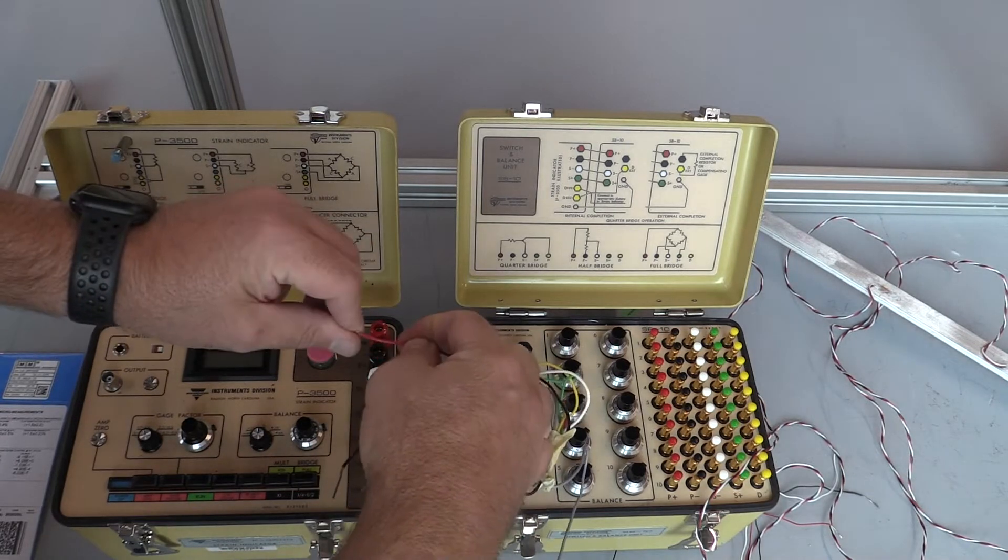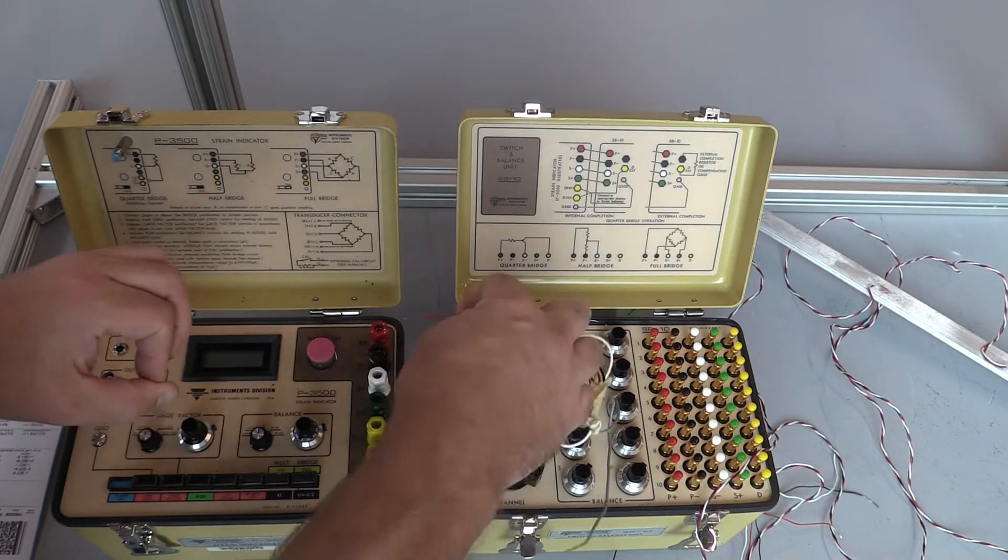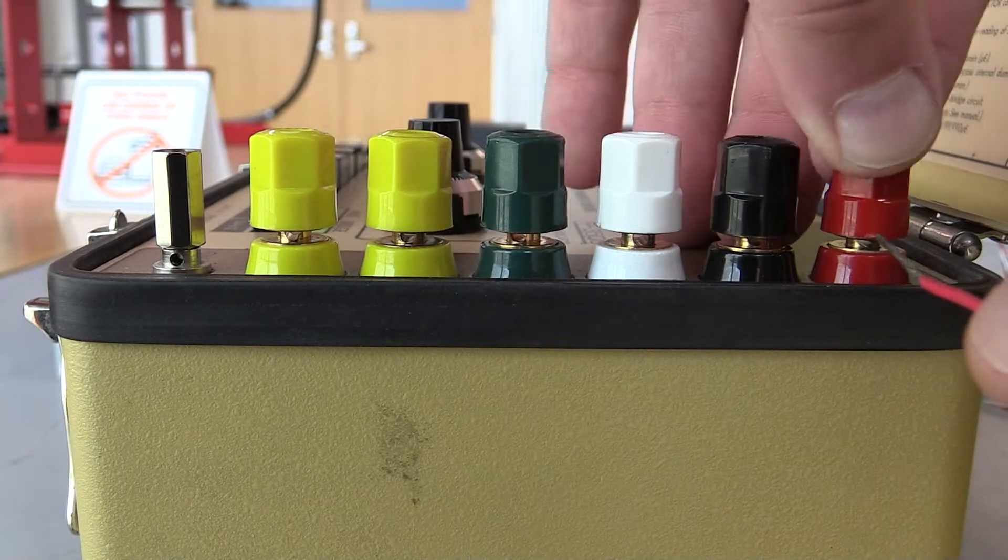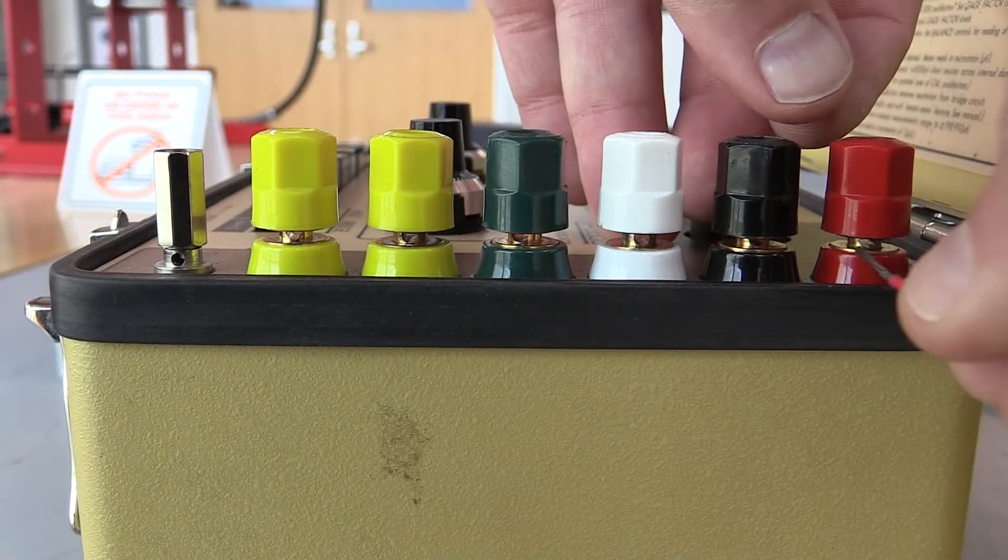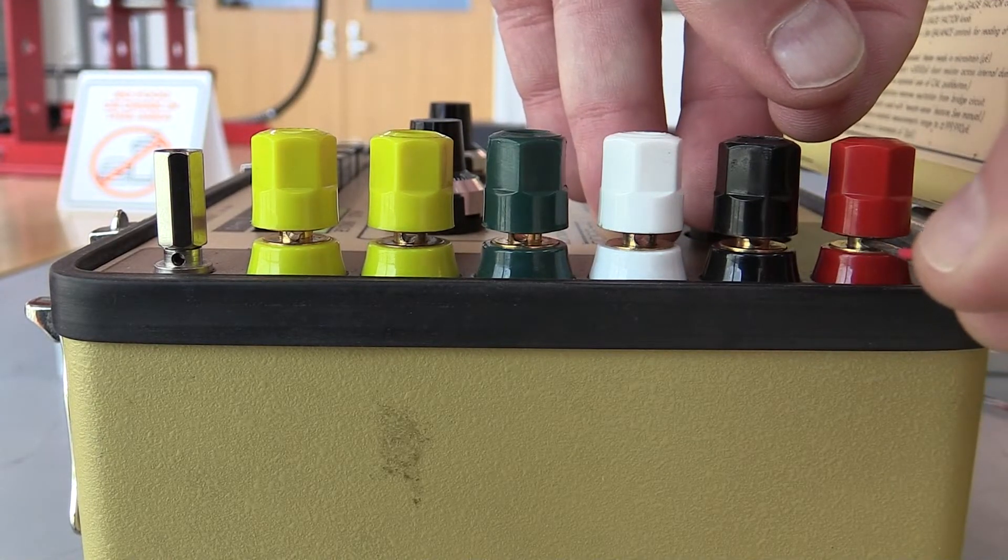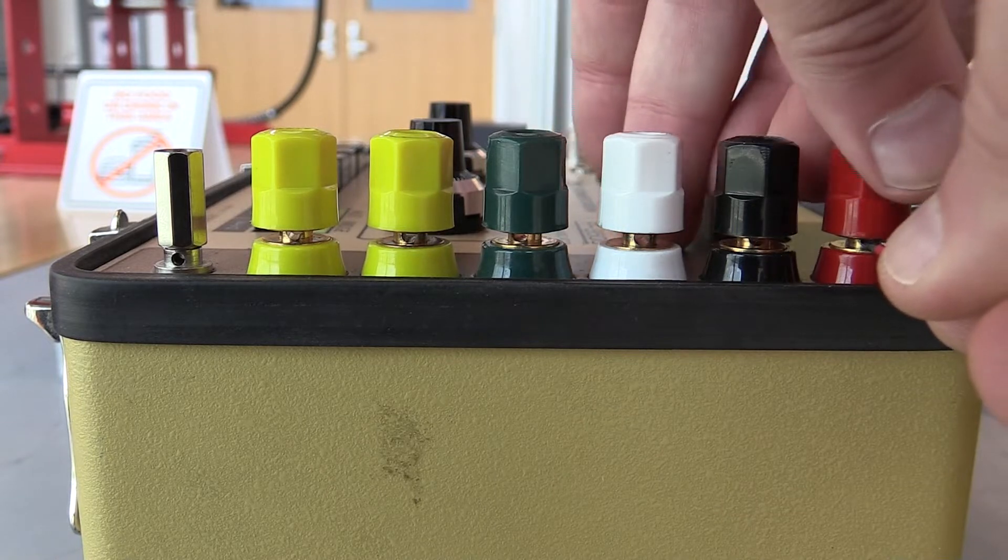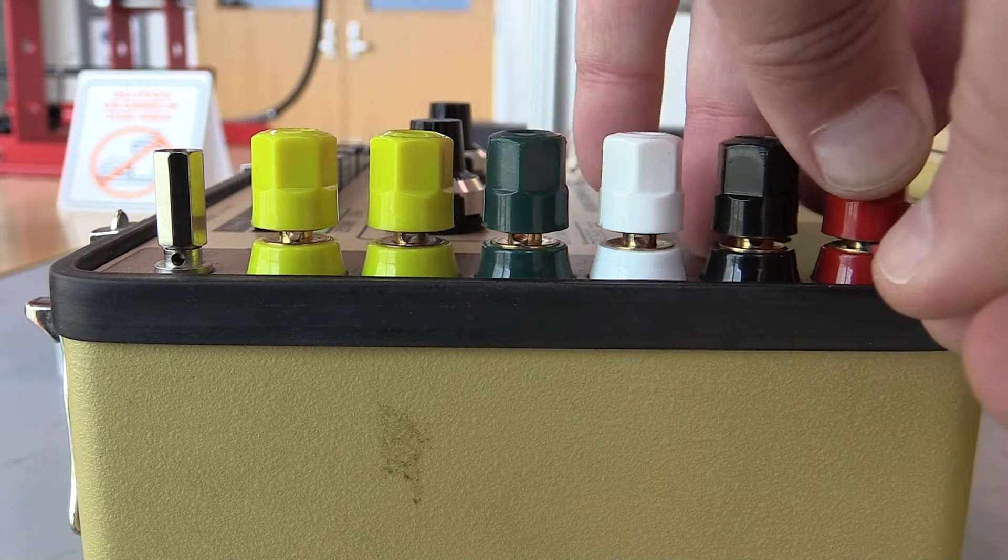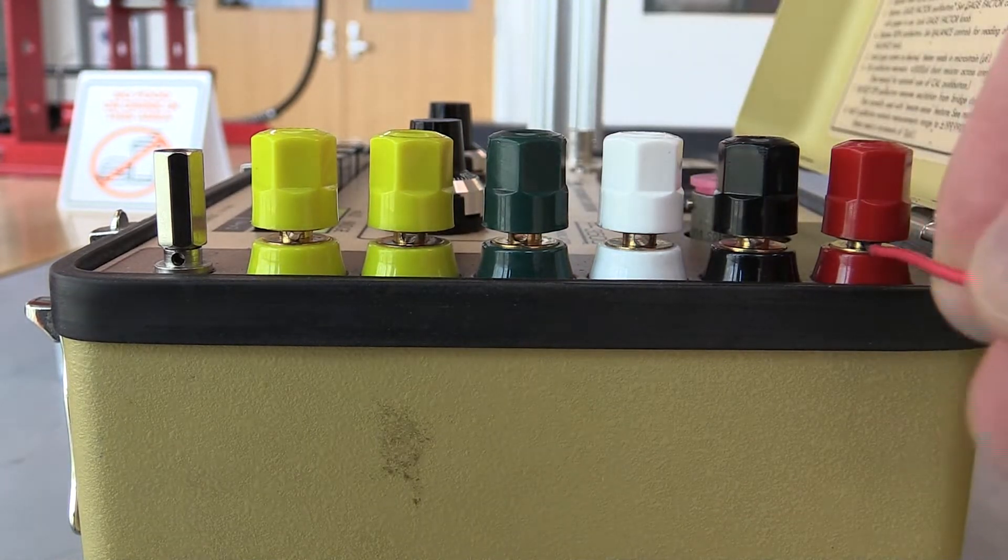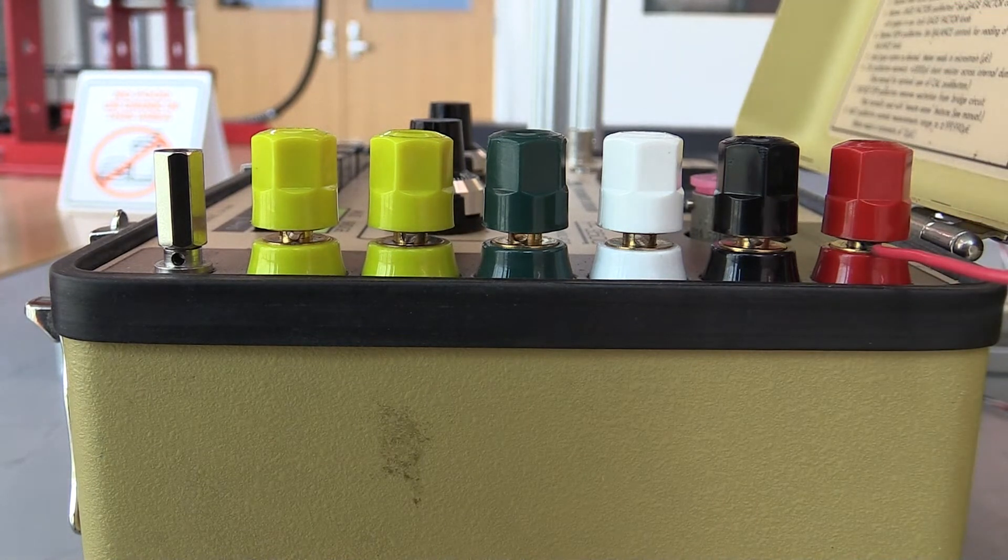And what you want to do is make sure that you're clamping onto the exposed wire portion. You're going to back this off. There should be a hole in that post. And what you're going to be able to do is feed that wire in there and then screw that down on there and check to make sure the wire is attached properly. Let's go ahead and hook the rest of these up.